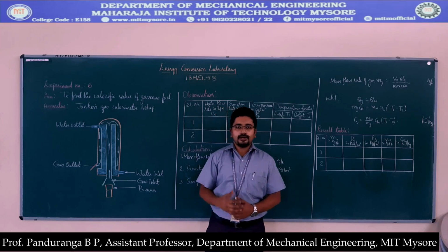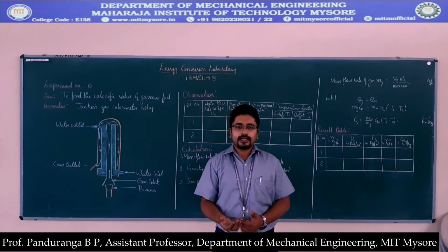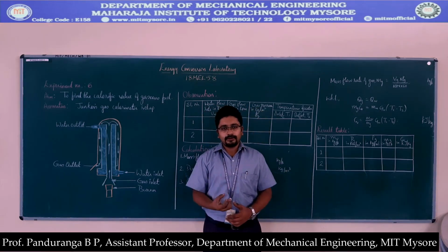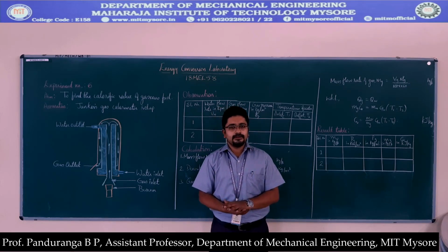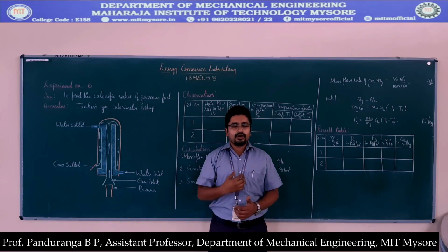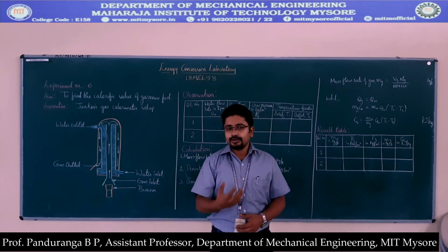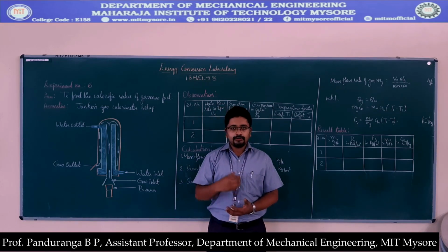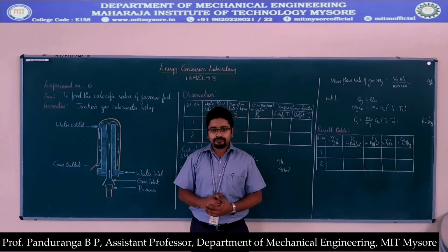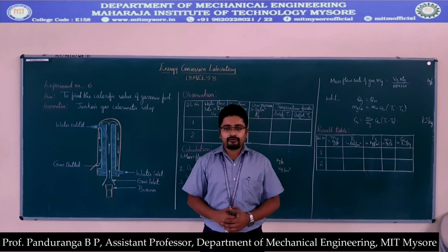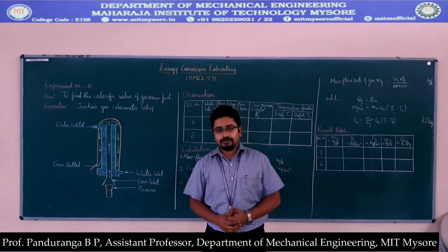In calorific value, we have two kinds of calorific value. One is higher calorific value and the other one is lower calorific value. When you burn a fuel and bring back all the products of combustion to the initial temperature of the fuel, then whatever the total amount of energy released, we call it higher calorific value. If you don't bring the combustion products to the initial temperature of the fuel, then whatever the energy released, we call it lower calorific value. So here, with the help of Junkers gas calorimeter, we are going to find out the lower calorific value of the liquefied petroleum gas or LPG.